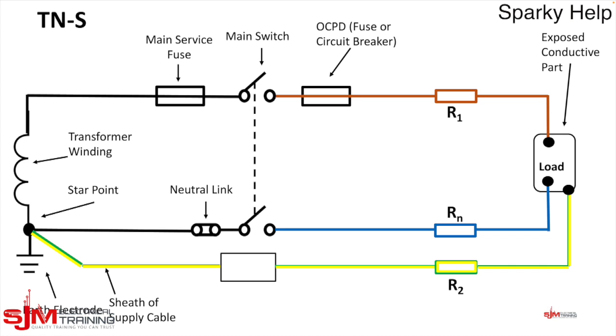We have our neutral link. We have our main earth terminal which could be within the board or external to the board, depending on your installation. We have an earthing conductor which connects from the MET to the sheath of the cable.